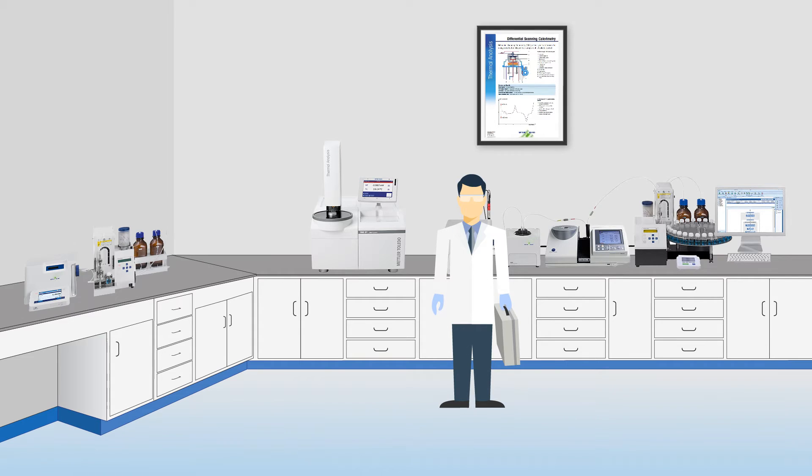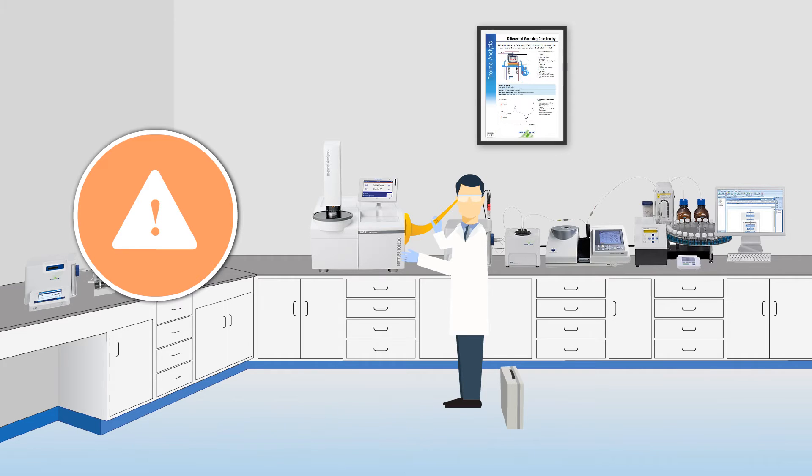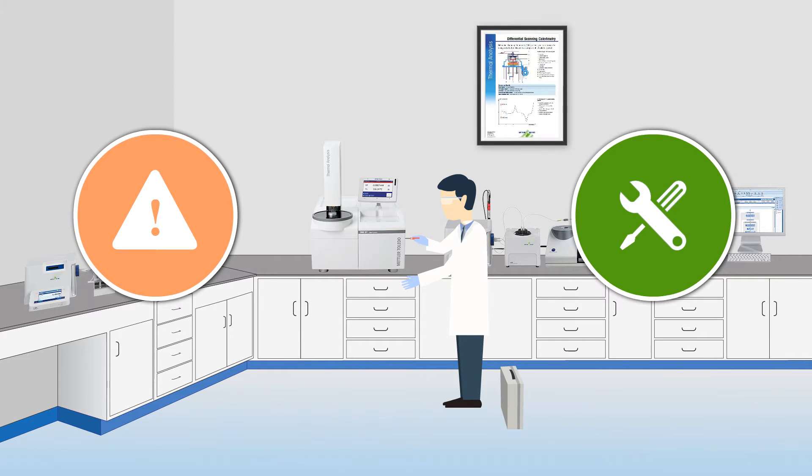In order to achieve accurate results, an instrument has to be regularly calibrated, which means determination of deviation from the expected behavior. If a deviation is detected, an adjustment is necessary to correct for the difference.